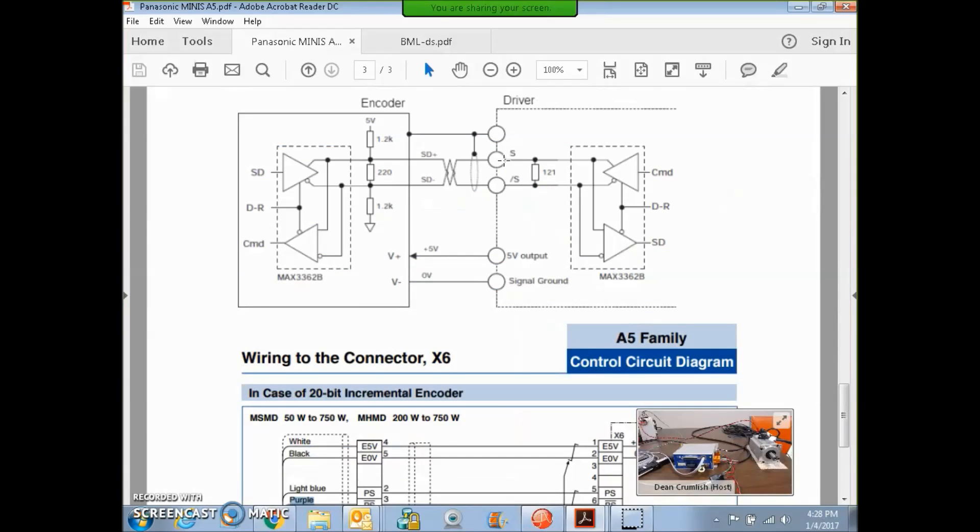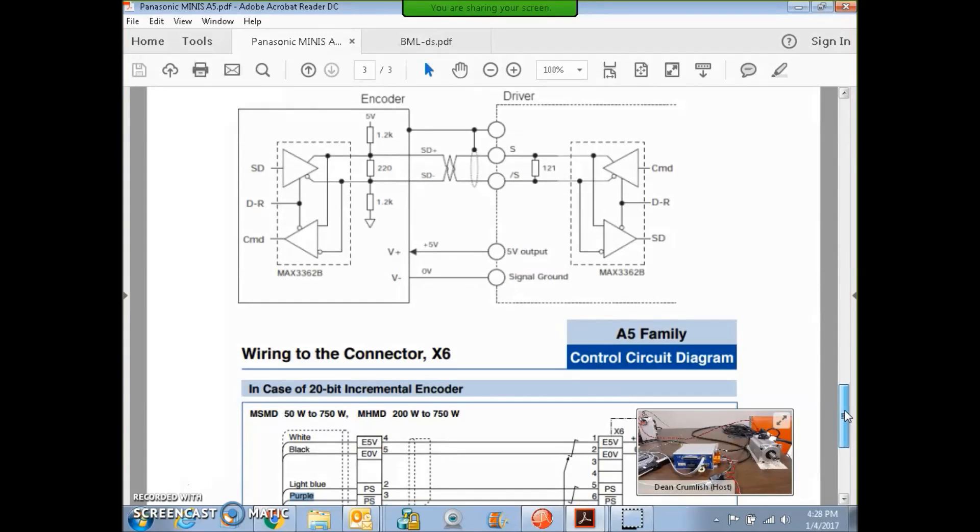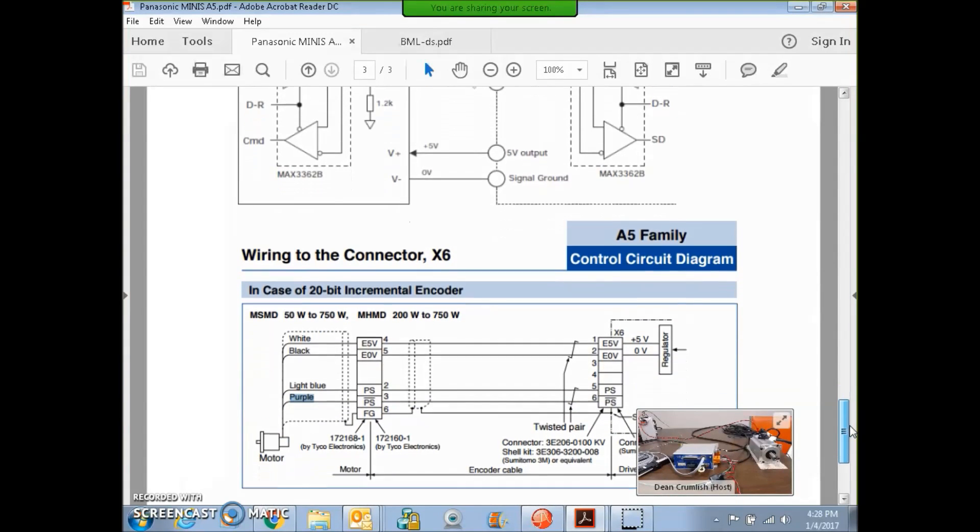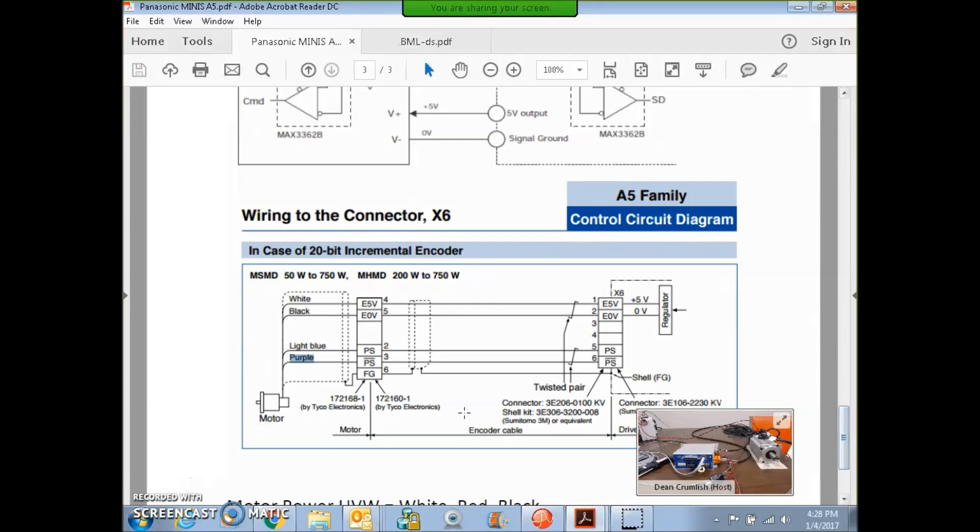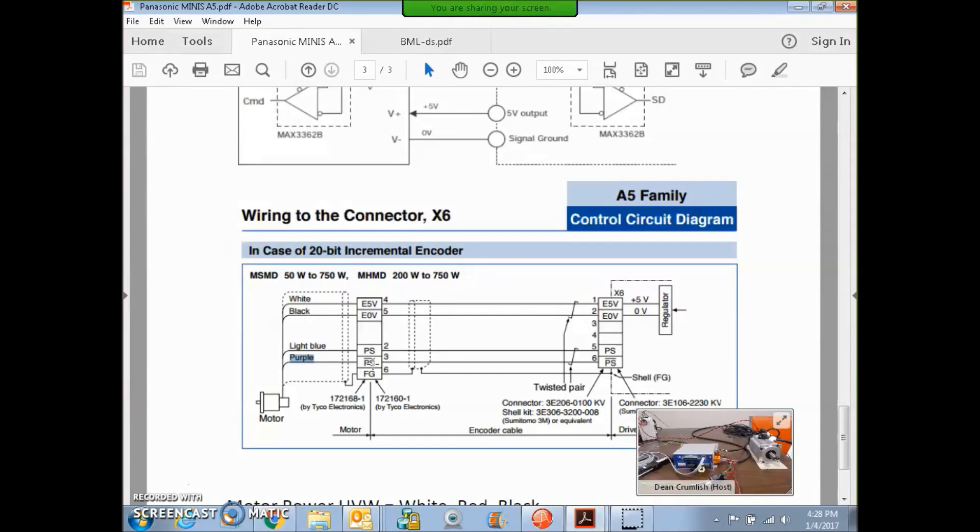The Copley driver takes S and S-not for bidirectional data and outputs plus 5 and ground. We connect this to the feedback device. The feedback device has plus 5 and ground, white-black wire, and the light blue and purple, so data and hat data or S and hat S.